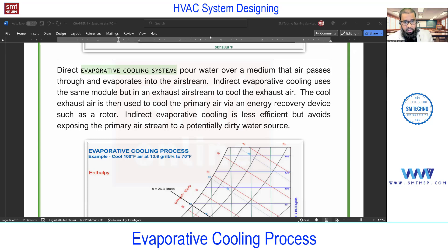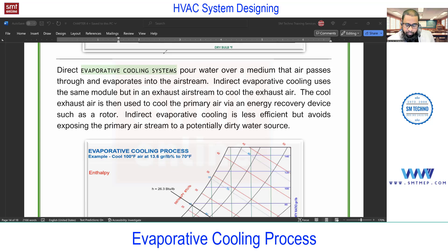The reason air coolers work efficiently in desert areas is because even in summer the humidity is less, so the air has the capacity to hold or extract more water at the time of evaporation. More evaporation means more cooling - because of evaporation of water, heat is extracted from the air so that the temperature of air can reduce. This is the evaporative cooling process.